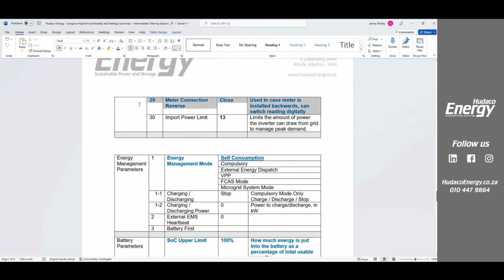Number 29 here, this is the reverse meter connection. So this is really where if you have installed the CTs backwards, you don't have to go to site. You just click enable and it'll turn the meter around digitally for you. Okay, very easy. Import power limit, as opposed to the other export power limit that we said earlier.